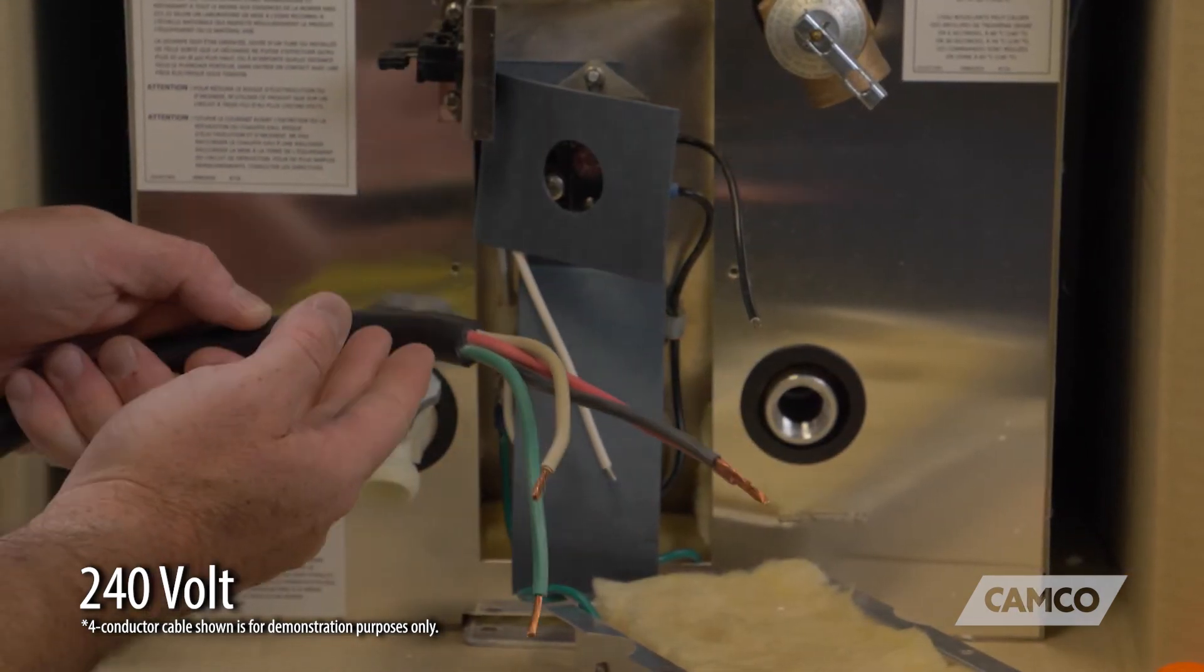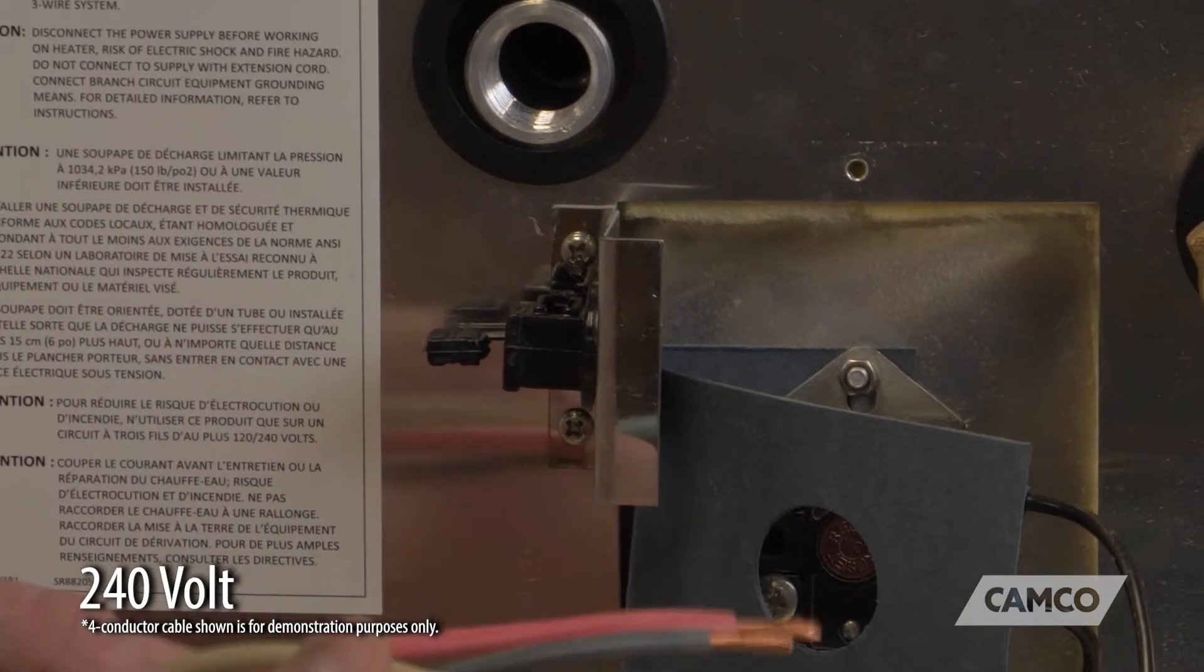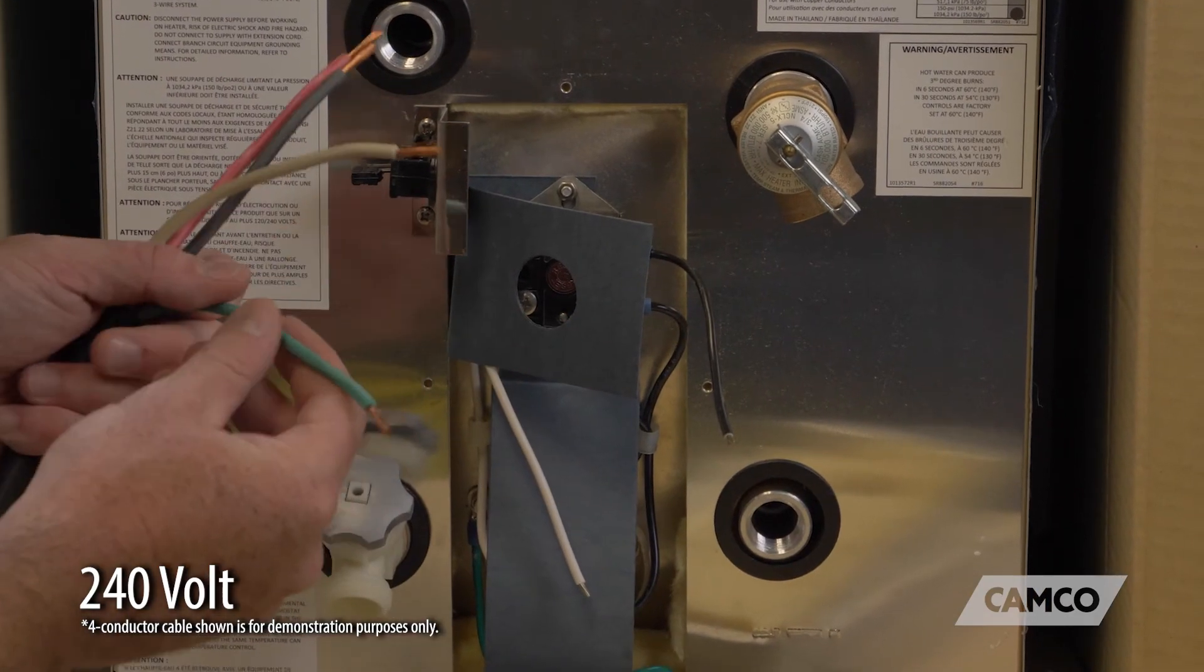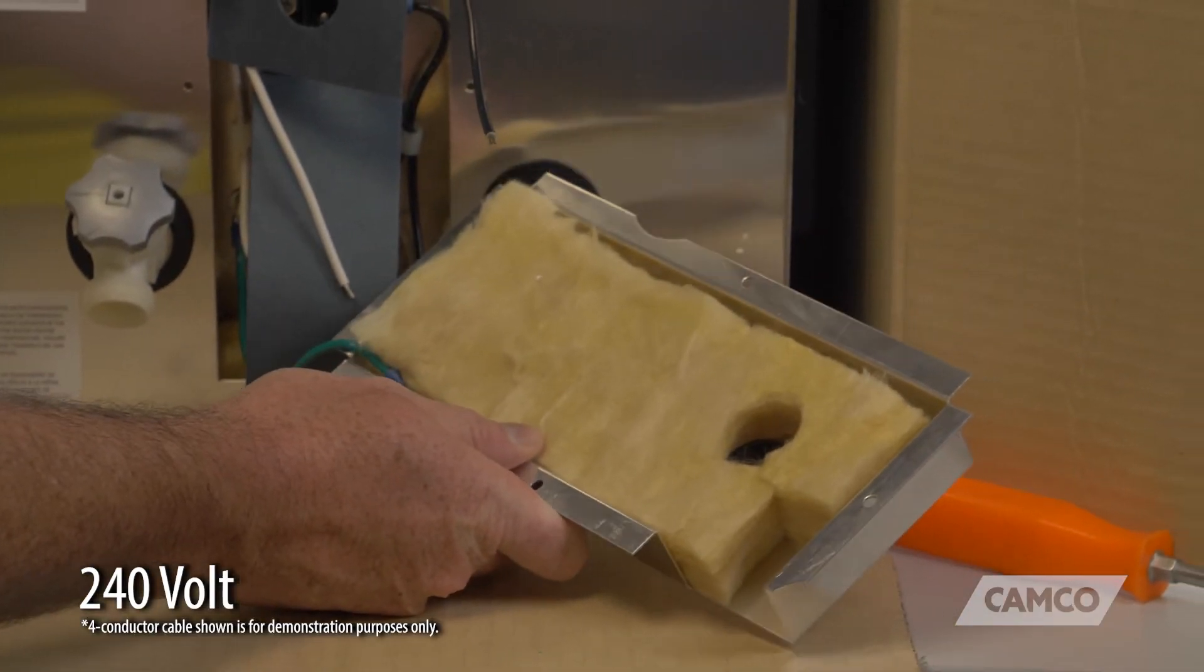In order to hook this up, you're going to run your cable through your strain relief clamp, and you're going to connect your green to your ground. This particular water heater, we've got the ground connected to the access panel. We stopped doing that after a certain date due to revision in the standards.